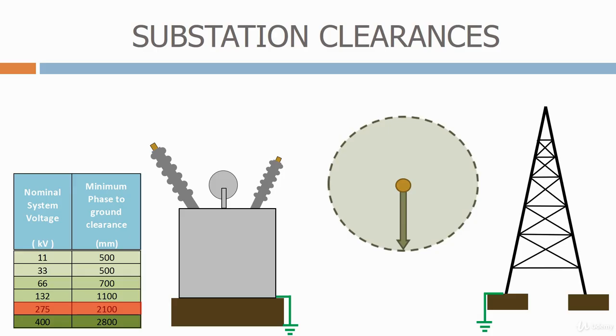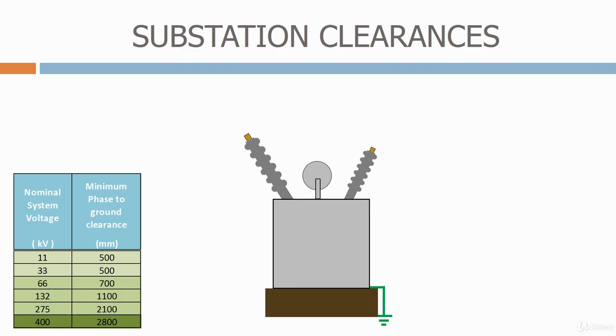Let's now look at a typical transformer. Imagine that the transformer has a 400 to 33 kV ratio. The live part of the transformer is the stem at the top of each bushing. Let's now draw a circle around these elements to show the phase-to-ground clearance distance. As long as the grounded transformer enclosure and all its fittings are outside these circles, we have met the minimum phase-to-ground clearance.